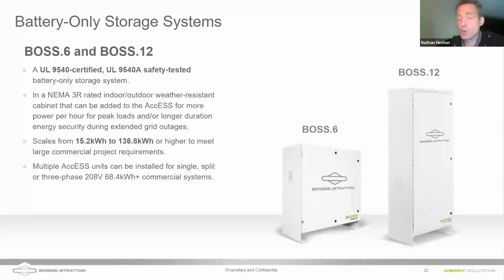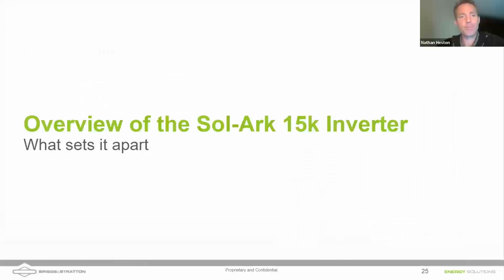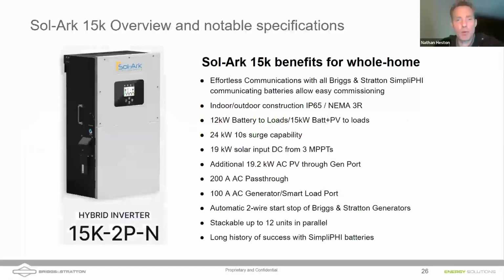and you want to do an outdoor install, you could also consider using these BOSS 6 and BOSS 12 enclosures. These are 9540 certified, 9540A tested. You can parallel, go all the way up to 136.8 kilowatt hours there. Very large systems if you want to parallel these. They've got built-in fans that turn on when the temperature is above a certain range, and these are helpful for outdoor installs. Let's jump into the specs of the Sol-Ark 15k.